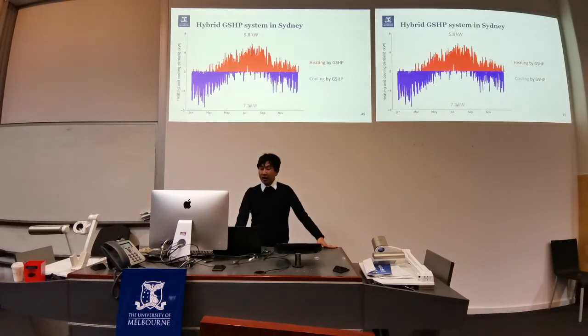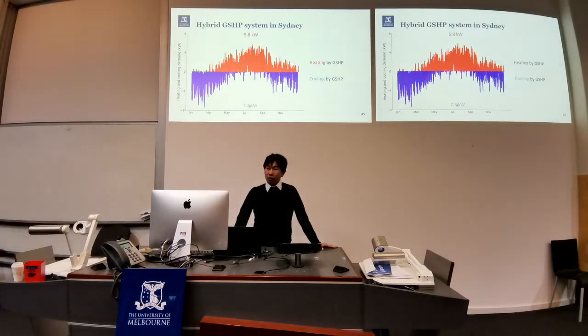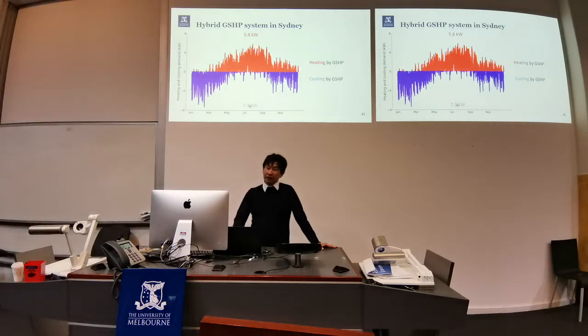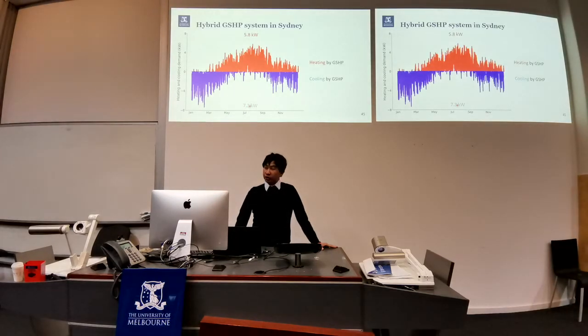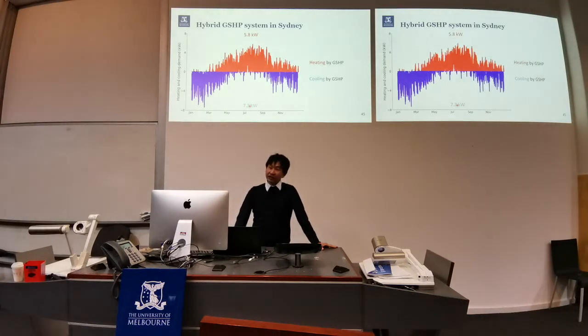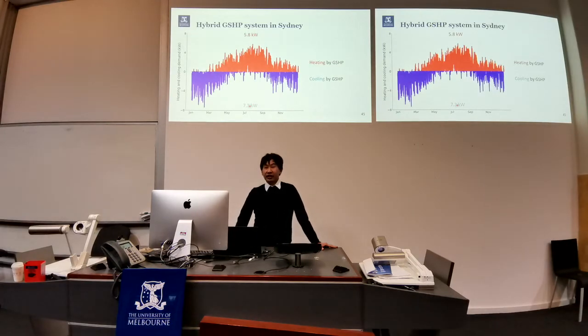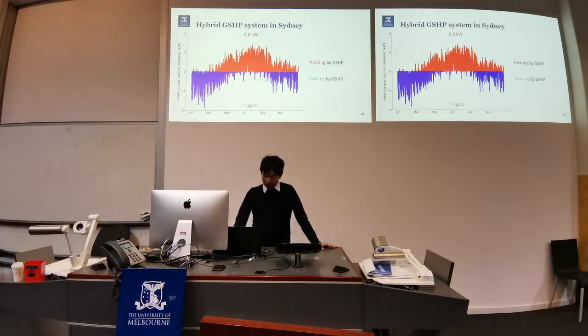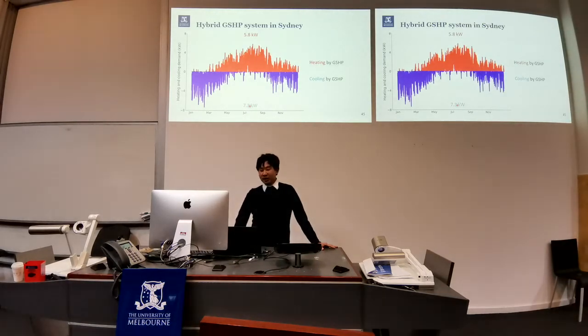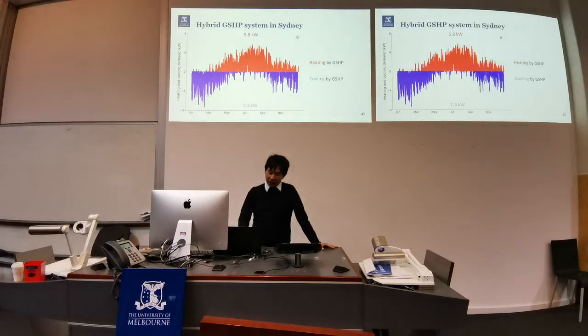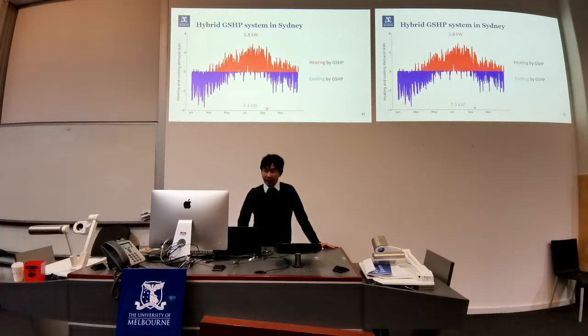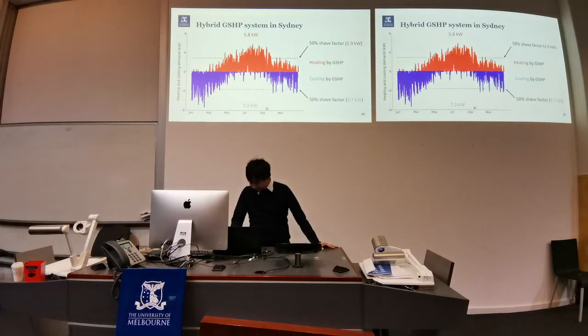So why do we consider a hybrid system? Previously, our monitoring data revealed that the temperate climate in Melbourne is mild enough that we can turn off the heating and cooling system for a significant part of the year. It turns out that the same is true for most Australian cities. So in this section, I will use the weather in Sydney as an example to represent the location with the most balanced climatic condition. In Sydney, the simulation from EnergyPlus suggests that the building requires about 5.8 kilowatts of heating and 7.3 kilowatts of cooling.